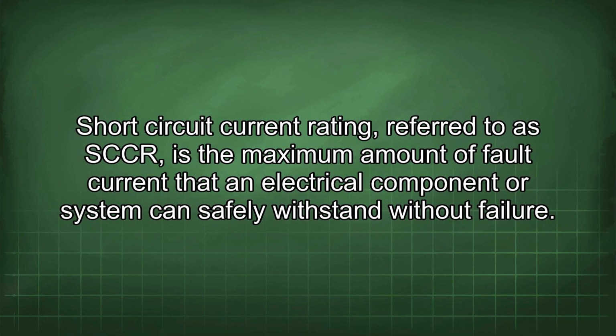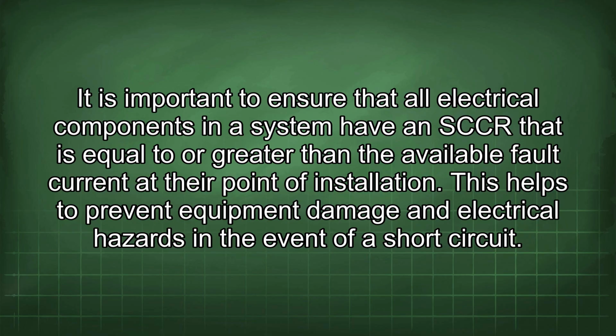Short circuit current rating, referred to as SCCR, is the maximum amount of fault current that an electrical component or system can safely withstand without failure. It is important to ensure that all electrical components in a system have an SCCR that is equal to or greater than the available fault current at their point of installation. This helps to prevent equipment damage and electrical hazards in the event of a short circuit.